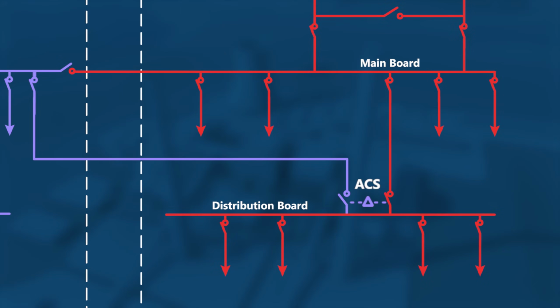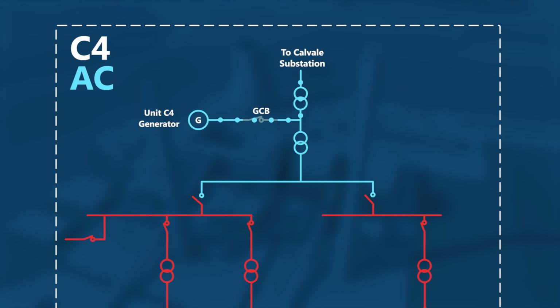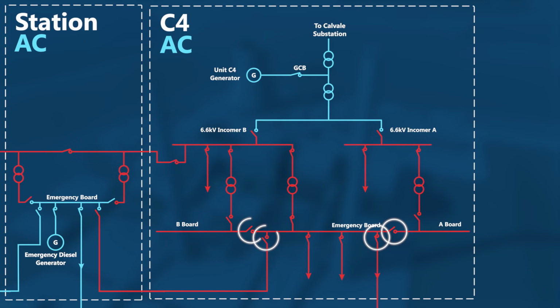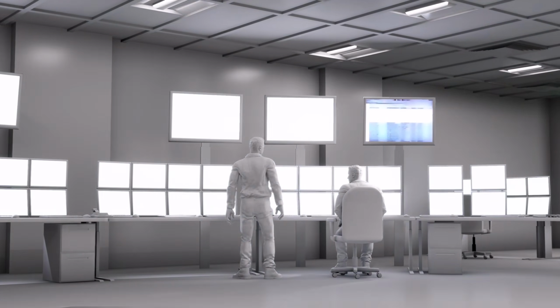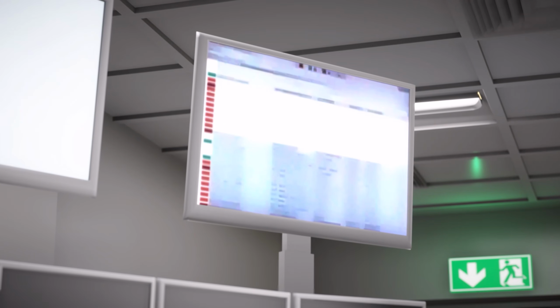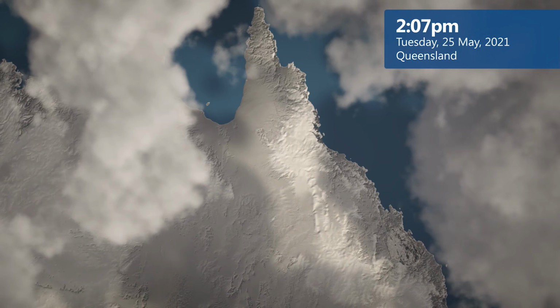Because the automatic changeover switch was unable to function in automatic mode, DC supply could not be rerouted to C4. This loss of DC meant the unit couldn't be disconnected from the grid and would motor for the next 34 minutes. It also prevented the AC system from being reconfigured to receive power from the emergency diesel generator. Operators had no visibility of the unit and were bombarded with more than 15,000 alarms. With no way to safely regain control of the unit, at 2:07 p.m, the incident reached its conclusion.